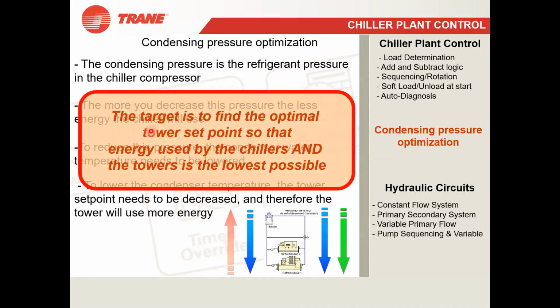So that, we will not do manually, it is never possible. But the chiller plant manager logic will be such that it will target finding the optimal tower set point, so that whatever energy is getting used is actually optimal. And that way maximum efficiency will be provided by the chillers and towers, and the lowest possible energy will be used by them.